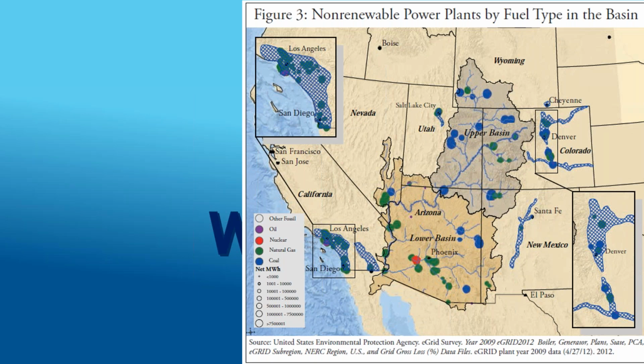I want to talk a little about natural gas, which maybe goes to the gentleman's point. Something has happened in natural gas power production over roughly the last 50 years, but really implemented in the last 5 or 10, which is combined cycle natural gas plants. A combined cycle plant basically has a jet engine that burns natural gas, and the shaft of that engine turns a generator. But the waste heat - the 1,000-degree air blown out the back of the jet engine - gets routed into the boiler for the Rankine cycle we just talked about. So we're using a Brayton cycle to directly create electricity from natural gas, then taking the waste heat from that process, putting it into a boiler, and running a Rankine cycle. As a result, the water use intensity of a combined cycle natural gas plant is about 200 gallons per megawatt - a substantial reduction compared to other methods.